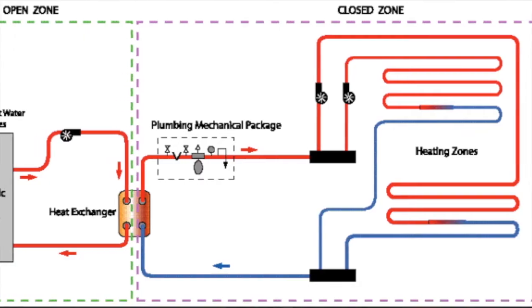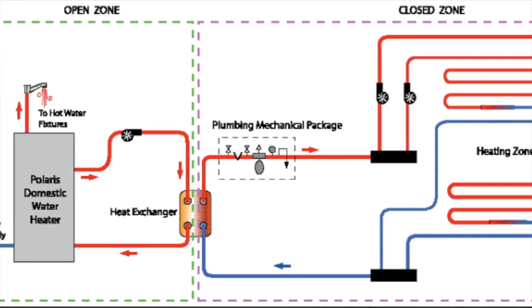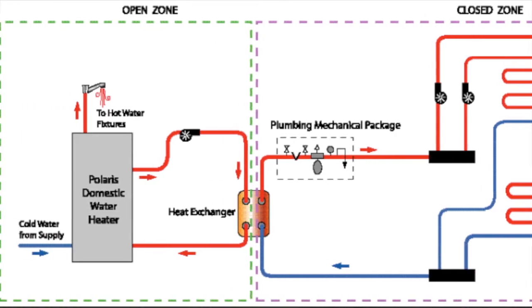Radiant floors are known for their superior comfort levels, and simulations in the IES virtual environment prove that the percentage of people dissatisfied with the thermal comfort per ASHRAE 55 was less than either of the forced air systems that we tested, even at a lower temperature set point. Although the radiant floor is an ideal choice for heating the building, it doesn't provide any ventilation or humidity control.